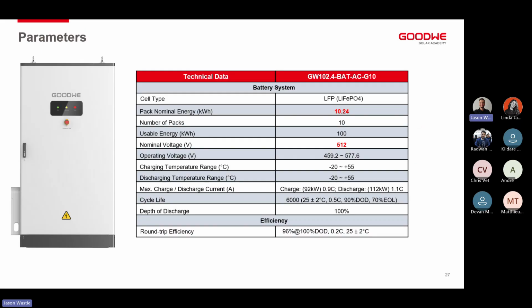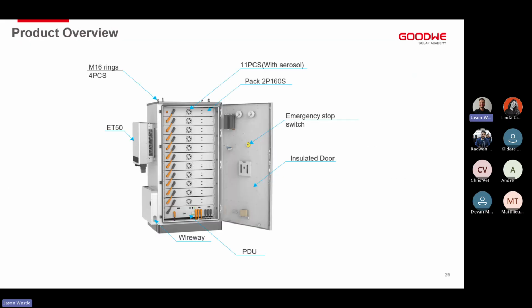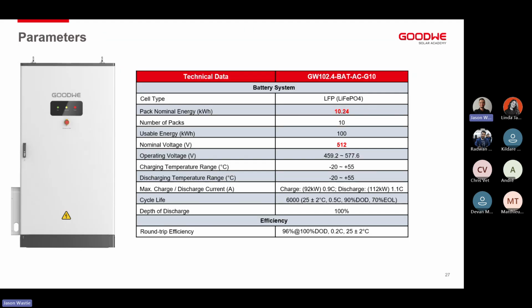This is just a quick look at the battery itself. It has got 10 packs of 10 different modules. If we go back, you'll count there are 10 modules. Every module is a total of 10.24 kilowatt hours, with a usable energy in total of 100 kilowatt hours. This is not scalable inside the same cabinet, as this cabinet does get pre-manufactured and pre-assembled at our factory.